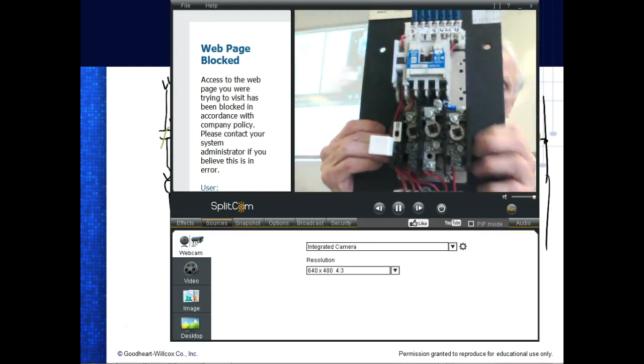So these are the contacts. They're all sealed in. So up here, this would be L1, L2, L3. These are our power. And down here, these would be what we call T1, T2, T3. This is where the motor actually hooks in. And all these other contacts, we call them auxiliary contacts. These are contacts that don't have to handle power. So it would be stupid for me to use a contact that's rated at 500 amps for a seal-in circuit.